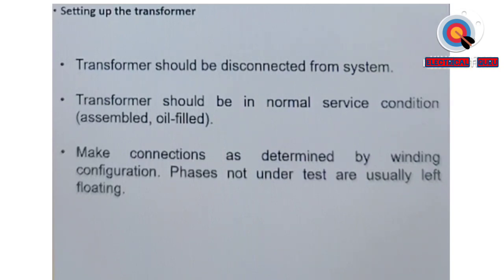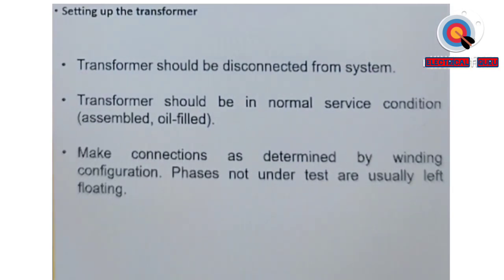The transformer should be in normal service conditions. When we say normal service condition, it means fitted with bushings and conservators, and filled with oil, as if it is in normal service. Make connections as determined by the winding configuration. Phases not under test are usually left floating. So we are not earthing those terminals, we just leave them floating so that they do not have any influence. If we try to earth them, then there will be some circulating current flowing, and then the whole impedance calculation would be affected. All other terminals should be left open and floating.